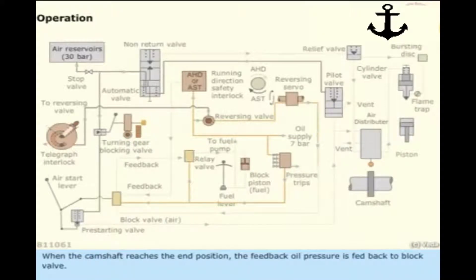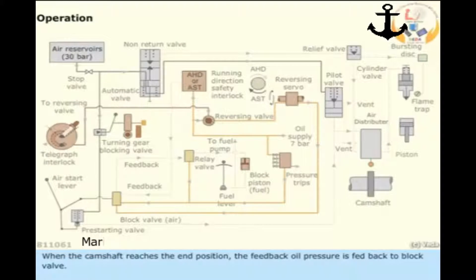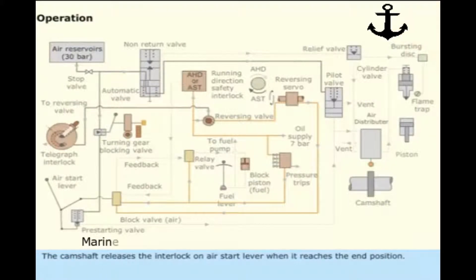When the camshaft reaches the end position, the feedback oil pressure is fed back to the block valve. The camshaft releases the interlock on the air start lever when it reaches the end position.